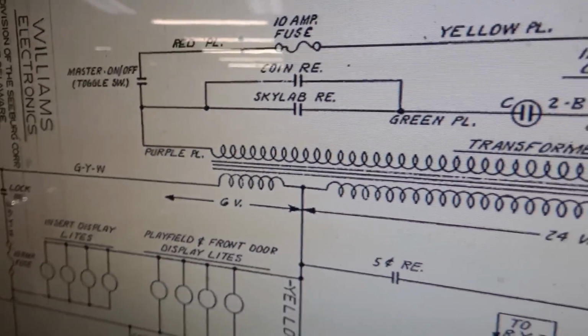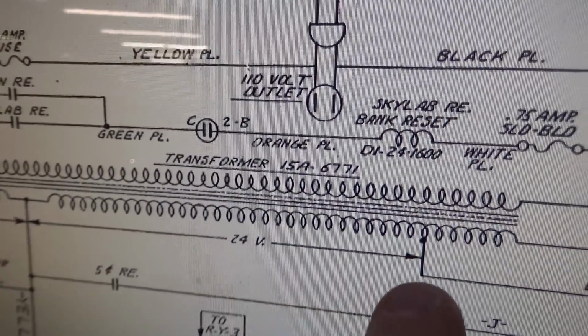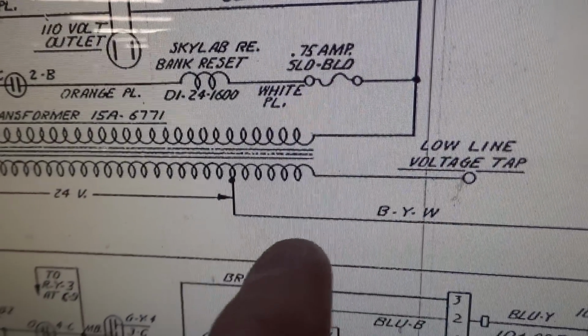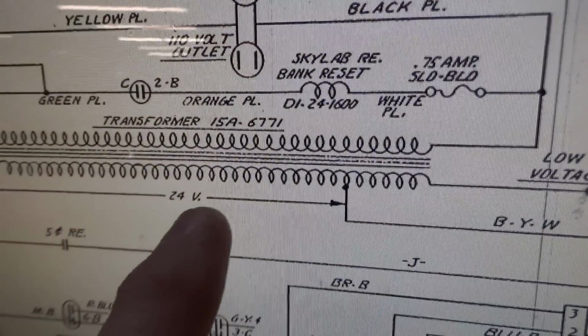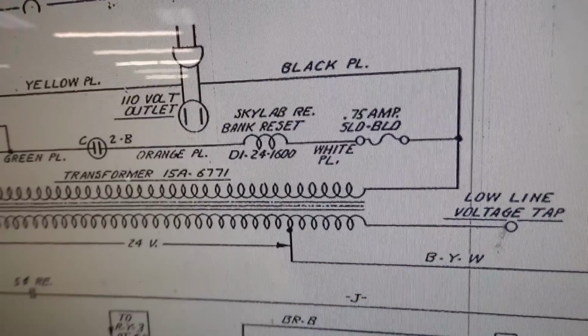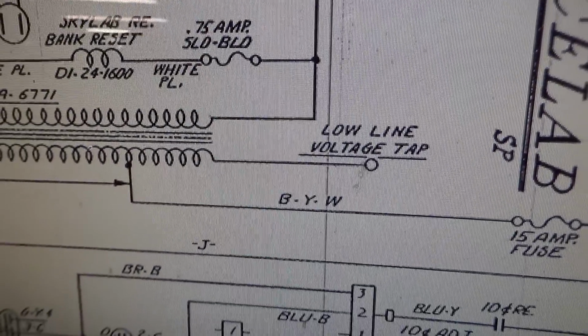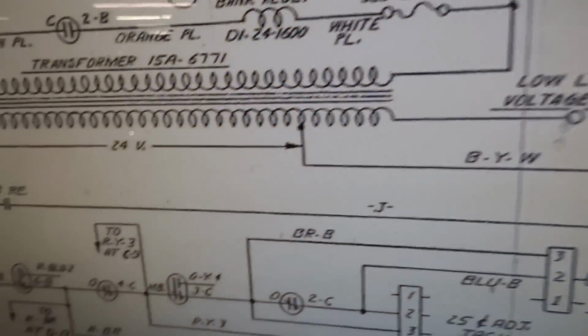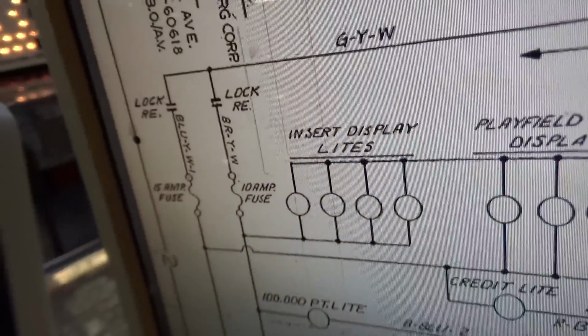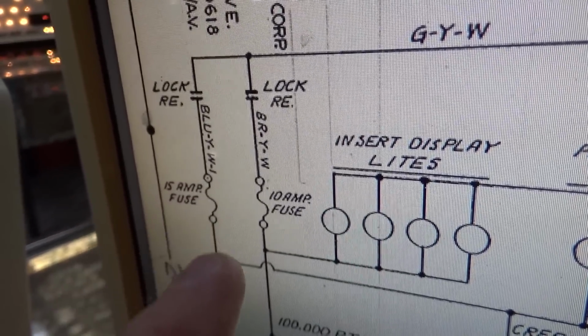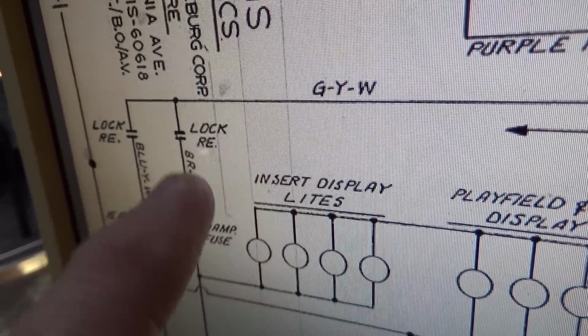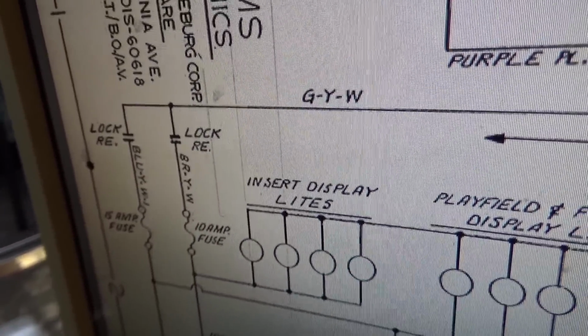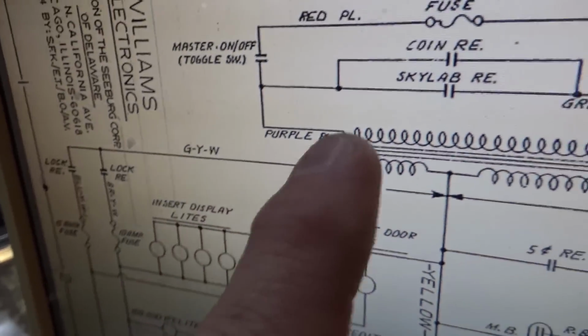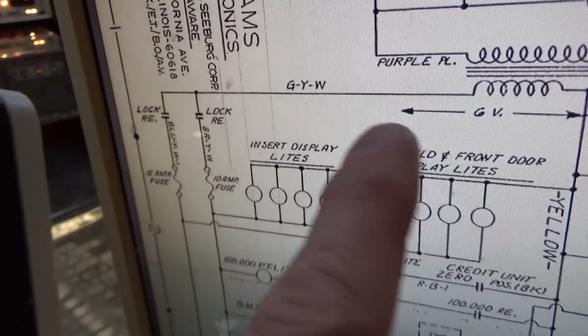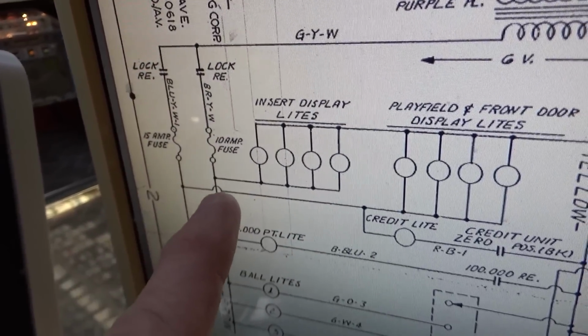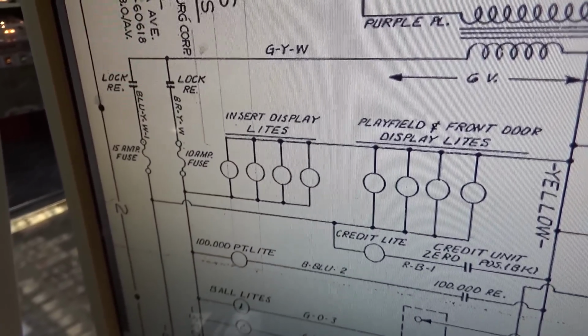...and 24 volts between these two lugs. Now notice there is another winding here. You can move this line to here, which will raise this voltage up if your line voltage coming in is lower than 110. But no matter what you do, all of the coils will work through a 15 amp fuse. Over here you have two fuses, a 15 amp and a 10 amp. So let's say you put the 10 amp fuse in, you will get these lights to come on as long as the transformer has power and it's got its voltages. If that fuse is in, you will get insert display lights to come on. The insert is the back box.